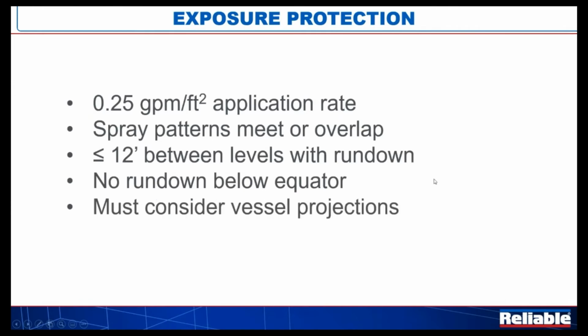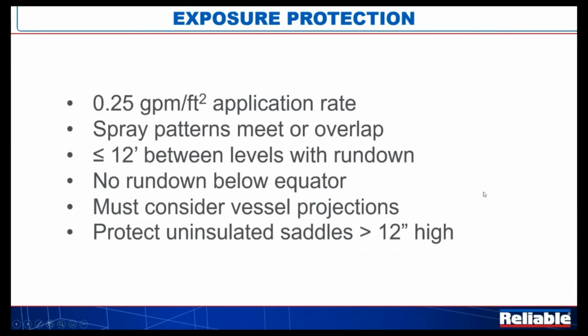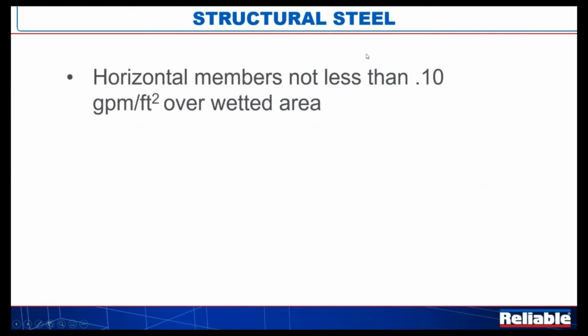If there are projections off the vessel, manholes, pipe supports, whatever they might be, you've got to look at those and consider whether or not the water is going to actually get to the underside of those. So look at the projections, make sure they're adequately protected. And then any uninsulated saddles that are supporting those tanks that are more than 12 inches high need to be protected, need to be looked at either in concert with the existing nozzles or perhaps with their own nozzles. So how do we do that?